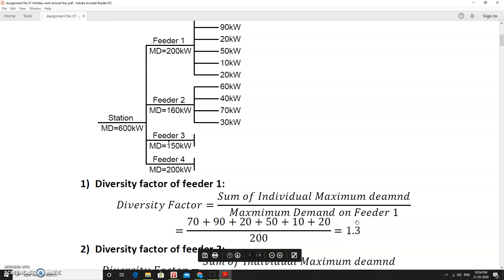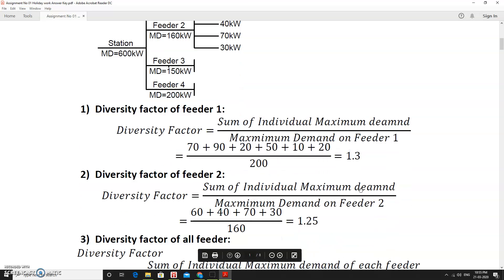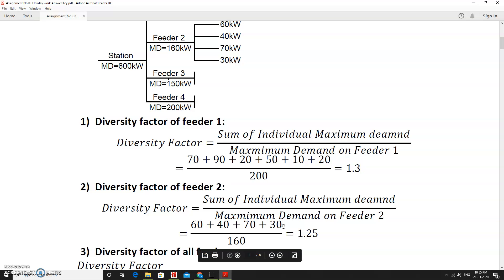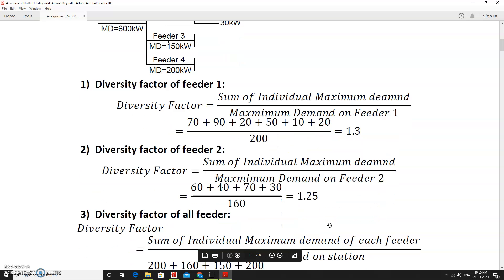Feeder 1 has a diversity factor of 1.3. For feeder 2, the sum of individual maximum demands is 60 + 40 + 70 + 30, divided by the feeder maximum demand of 160 kW, which gives a diversity factor of 1.25.